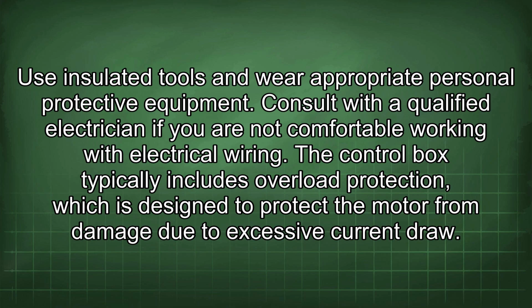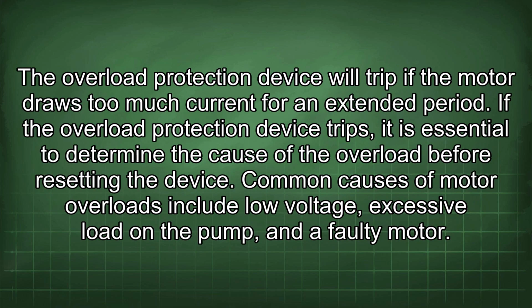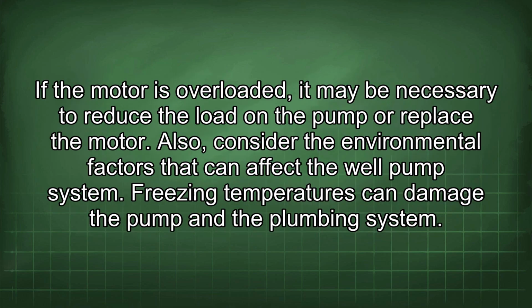Consult with a qualified electrician if you are not comfortable working with electrical wiring. The control box typically includes overload protection, which is designed to protect the motor from damage due to excessive current draw. The overload protection device will trip if the motor draws too much current for an extended period. If the overload protection device trips, it is essential to determine the cause of the overload before resetting the device. Common causes of motor overloads include low voltage, excessive load on the pump, and a faulty motor. If the motor is overloaded, it may be necessary to reduce the load on the pump or replace the motor.